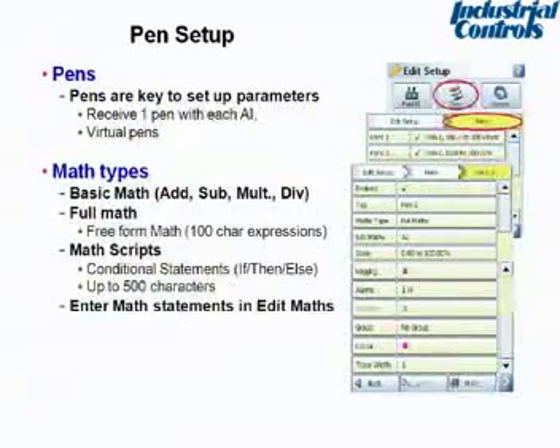Then the second part of the configuration, whether you do it on the recorder or in the configuration tool, is setting up the pen. So for example, if you had a type J thermocouple, it would be unlikely that you want to display minus 55 degrees Fahrenheit to plus 2400.